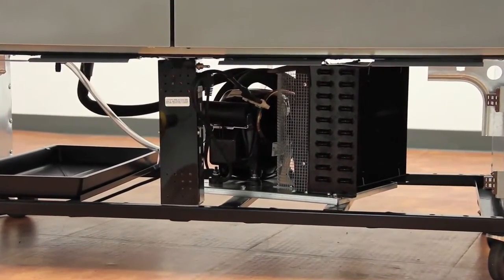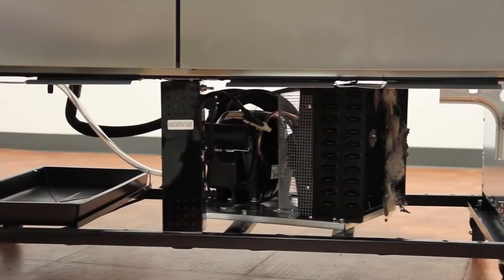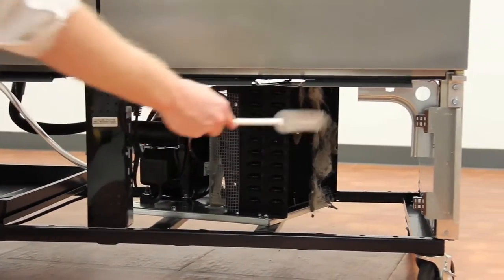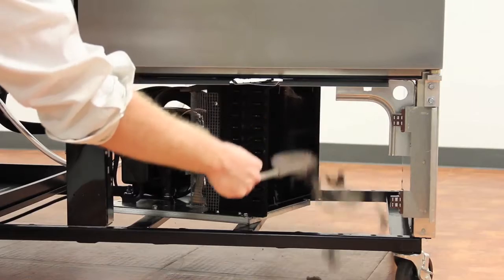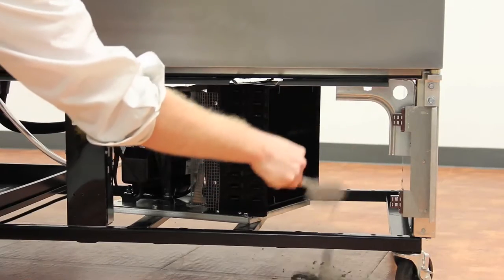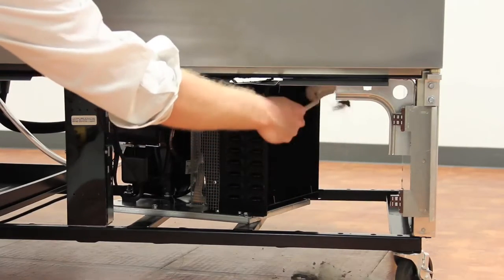Step three, clean off the accumulated dirt from the condenser coil and fan with a stiff bristle brush. Remember to brush up and down the coil and never side to side as this could bend the fins on the coil.